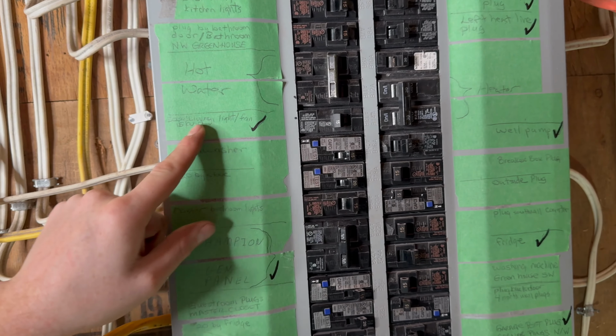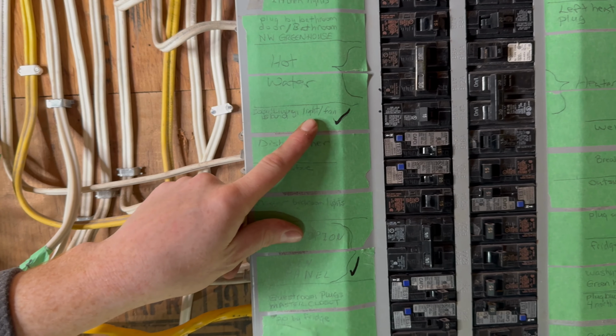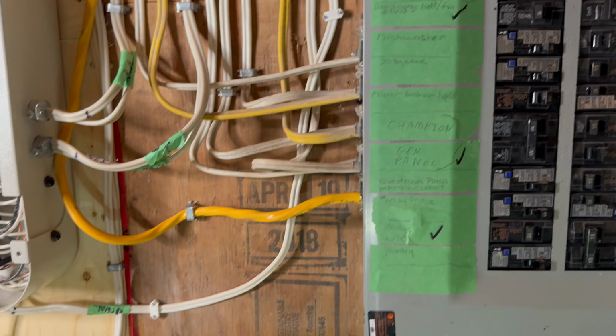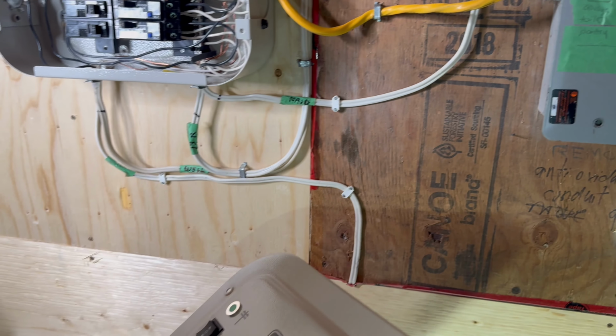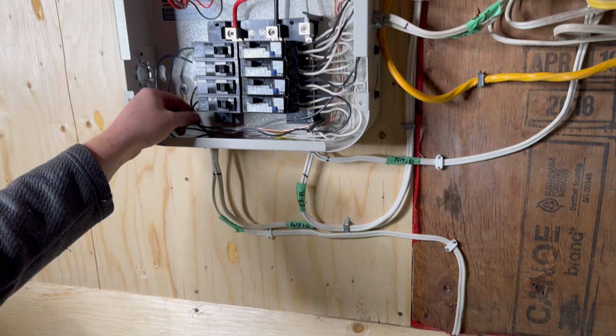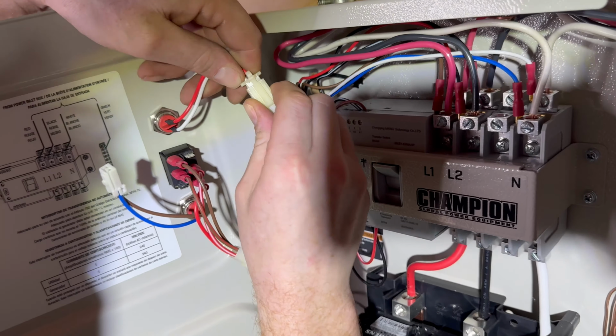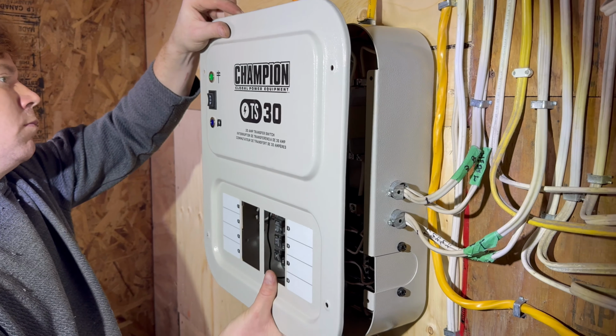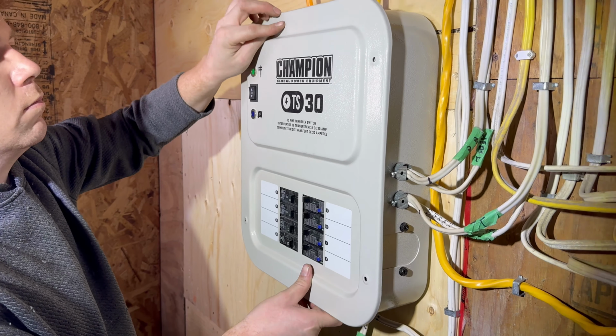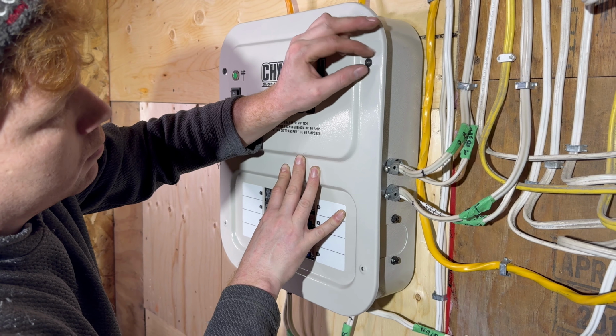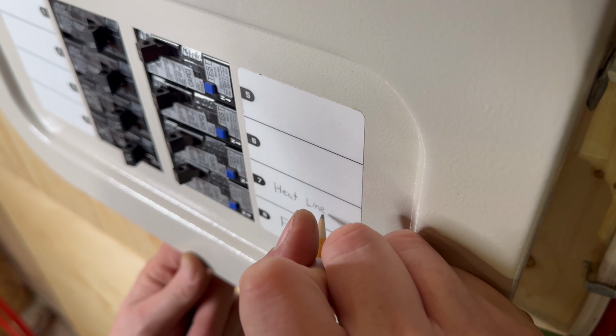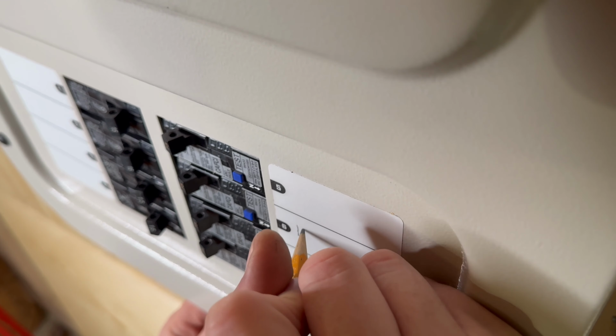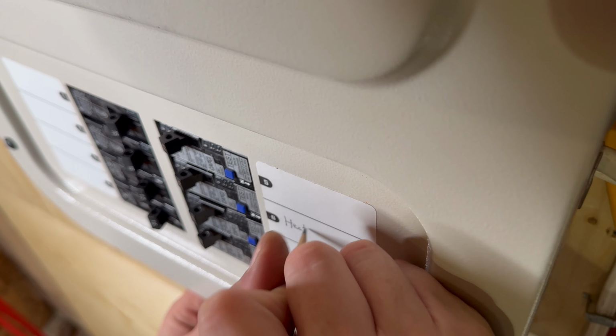Double check everything and update any of the labels that need to be changed on your panel. And then it's time to reinstall the cover on the transfer switch. So you make that wiring connection, replace the screws, and tighten them down. You should also mark the transfer switch panel with the appropriate labels for the circuits that it powers.